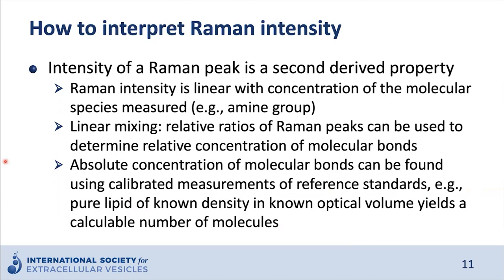For a given molecular species, the lower concentration detection limit is constrained by how efficiently it scatters light, since not all molecular vibrations scatter light equally. Typically one can easily measure down to roughly picomolar concentrations. When combined with surface enhancement — performing Raman near a nanostructured metallic material such as gold nanoparticles or silver nanostructured substrates — you can measure femtomolar or even single molecule amounts. That technique is known as SERS, or surface-enhanced Raman spectroscopy.